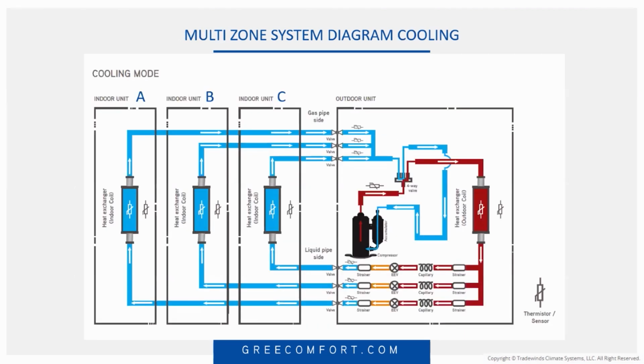Because all we're really doing here is the same thing, only we're adding a metering device for each indoor coil. We still only have one condenser coil, but we've added a metering device, and all we did was parallel our indoor coils to that one outdoor unit. But in order to do that, we've got to control flow into each one of those, and that's why you see these added thermistors. You're going to have a gas and a liquid thermistor for each circuit. So you've got a liquid and a gas.